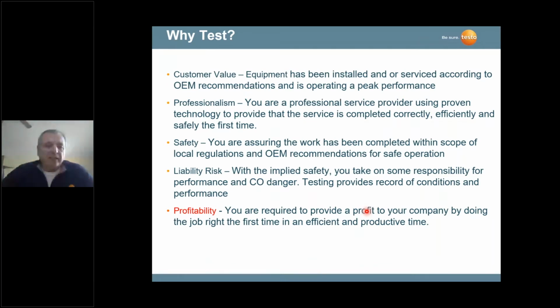Liability issues, certainly. We want to make sure that when we leave that appliance, whether it's a boiler, an industrial boiler, or a residential furnace, we feel good that we did the proper testing. We feel good about leaving that system in peak operating performance and safety. And it's also about profitability. All of us here today are here to make some money, and we want to make sure we do the job right the first time. We don't want callbacks or any type of return to the customer because something's not right in the combustion process.